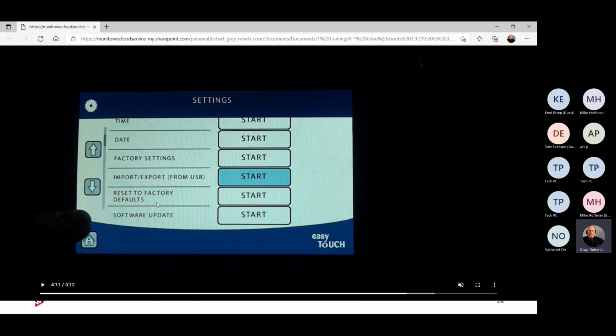I'm going to tell you right now, guys, if you reset it back to factory defaults, it's just like putting a brand new UI into the unit. Not only do you have to check the factory settings and put all the right date, the serial number and information back in it, you're also going to have to do all the calibrations again. So it stores that information. Just like if you reset factory defaults, you're starting from the beginning. It resets everything, including calibrations, recipes, everything.